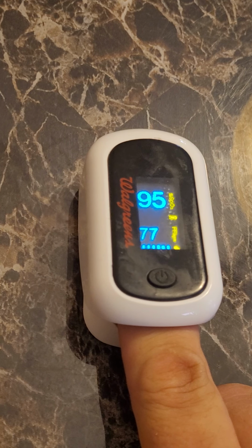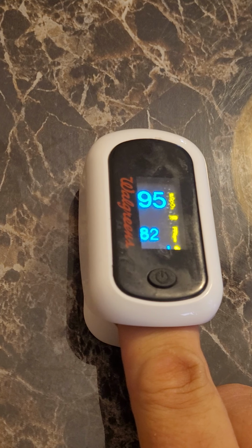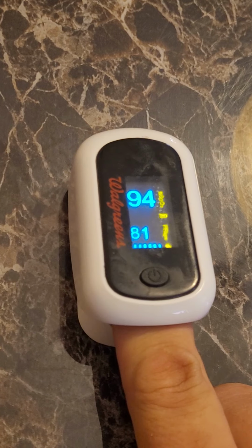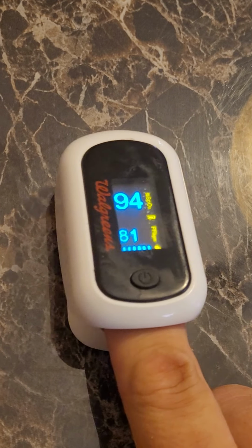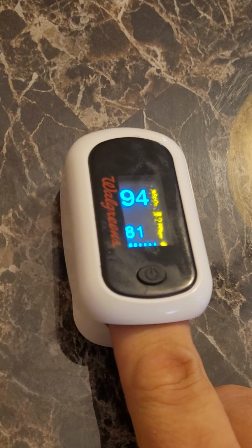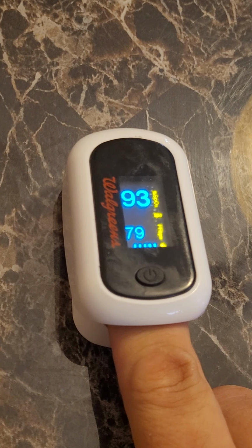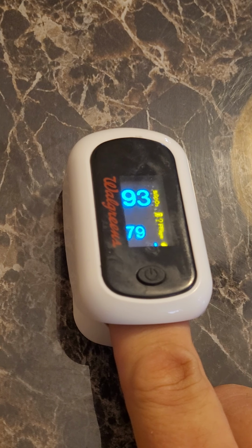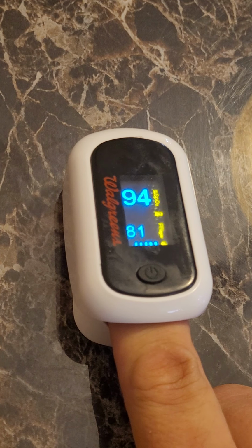Now, you'll see variation in pulse oximetry, and some of the things that can confound it include your hands being cold because your vasculature clamps down, making it more difficult for the device to get a good reading on it. A lot of movement will also confound a pulse oximeter generally, making it very hard to get a reading, so you need to hold still when measuring these values. And that's about it. So let's talk about the reasons why we'll confound these pulse oximeters and their functionality.